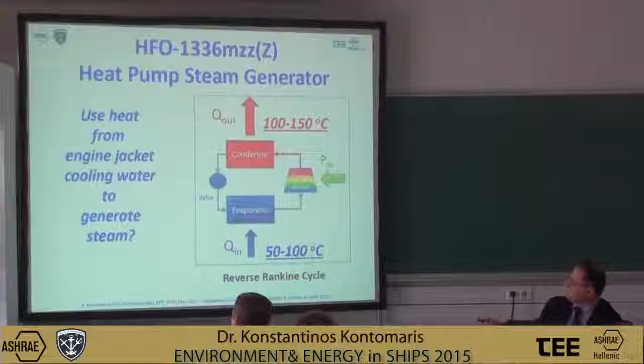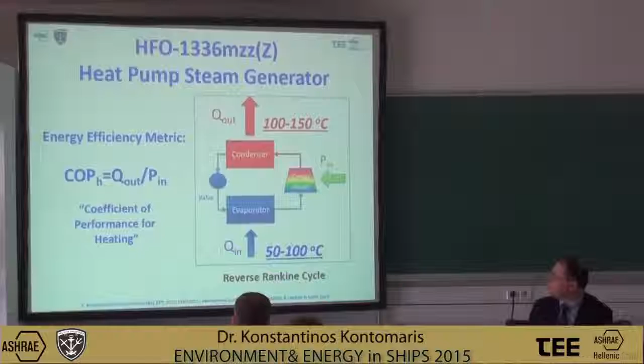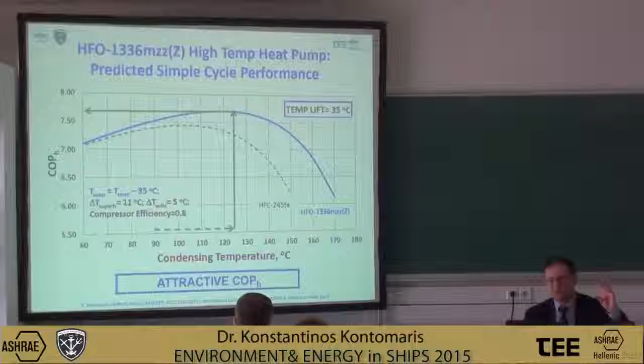So just to give you a sense of performance for this concept, the usual metric for performance or energy efficiency that is used for these applications is the coefficient of performance. This is nothing else than the amount of heat that you generate over the amount of power that you consume to run the heat pump. Basically what you get versus what you pay. So with the new fluid, you accomplish significantly high values for the coefficient of performance for various condensing temperatures. So here we're talking about producing steam. So let's say you want to run the heat pump to produce steam at 125 degrees. Then the coefficient of performance or the efficiency for this operation would be pretty high, above 7.5. What that means is for every single unit of power that you consume to run the compressor, you produce 7.5 units of heat at the temperature you want, and no higher, because then it would be wasteful.